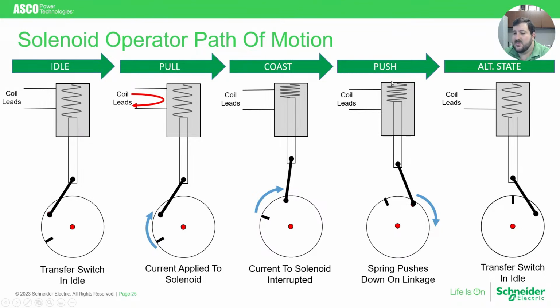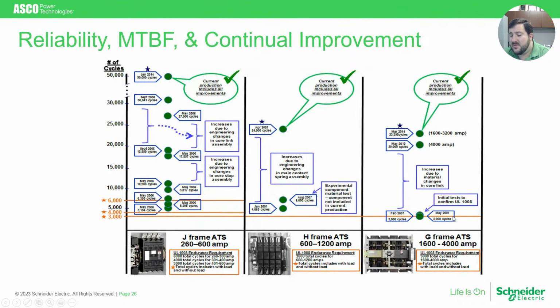It's really just a spring, a coil, and a shaft that actuates linearly, but then is converted to rotational motion with this assembly down here. And that's the heart of the operator in our transfer switches. And that's very important because it's actually a very simple design. And a lot of times people look at very complex designs and call that elegant, but elegance is really in simplicity. And simplicity leads to reliability, because the more complex something is, the more points of failure there are, the more tolerance stack-ups there are. So you want to keep the design and the operation as simple as possible.